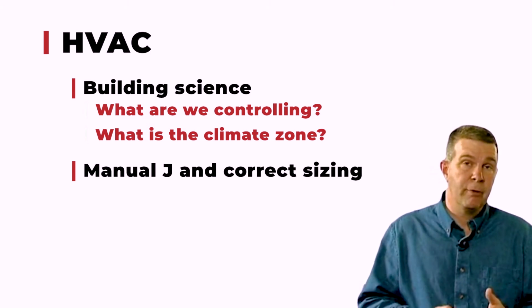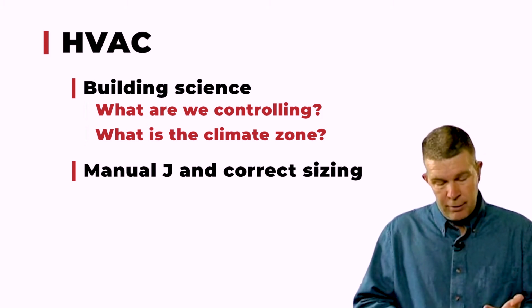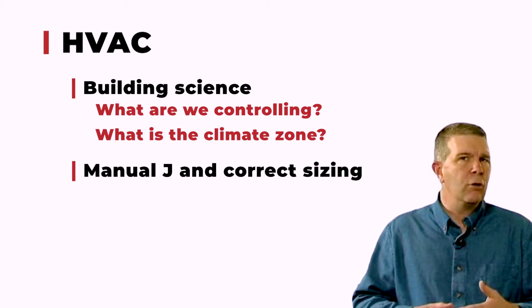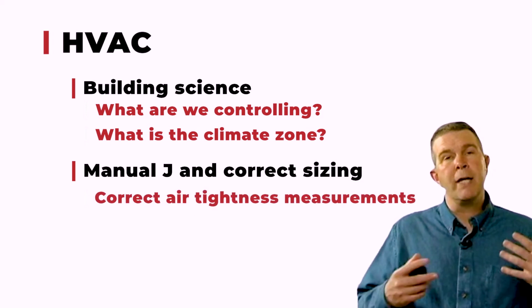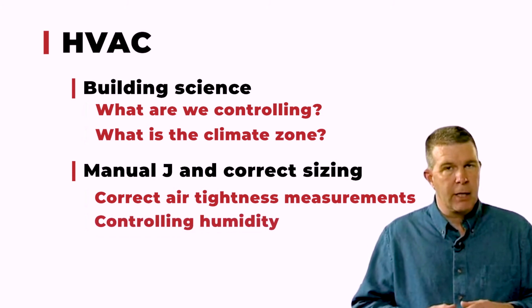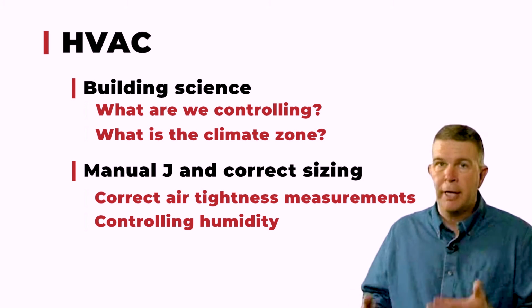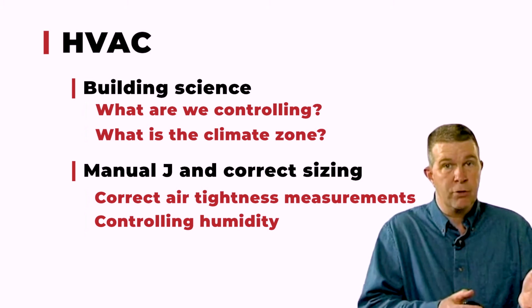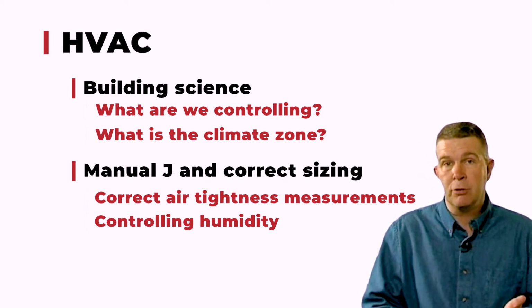How do we do that? It's commonly referred to as a Manual J calculation. Manual J calculation takes into consideration the R-values of all of your insulation from your slab all the way up to your roof assembly. It looks at the U-values of your windows. It looks at the type of foundation that you have, and it looks at the orientation of your shading and your light exposure, and it determines what that total BTU usage or its needs are in order to be properly heated and cooled. In order to do a Manual J calculation on a SIP house, you have to know what numbers should be plugged in order to get the right output. If you put garbage in, you're going to get garbage out. And if you're dealing with an HVAC contractor who has never designed or never worked with a Manual J when working with SIPs, they may be relying on too many things like rules of thumb, and they won't go through the scenario of a proper Manual J to get the real numbers.